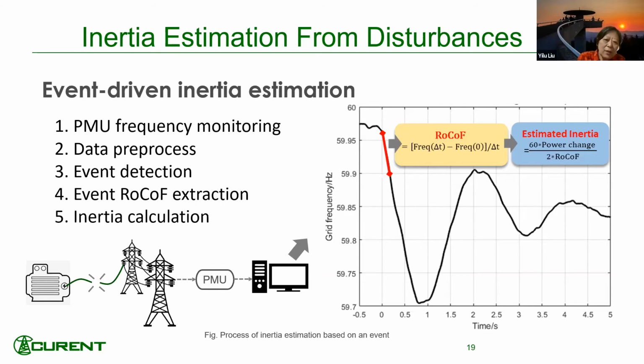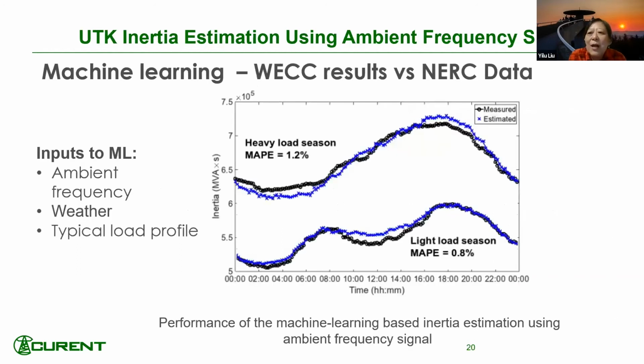I can actually monitor system inertia easily with collaboration with the utility company. If we're talking about real-time measurement, that's difficult because you don't have a trip every minute, and you don't want that to happen either. You have about one major generator trip maybe every day or every other day. That's typical, so you can't know your inertia every hour or every 15 minutes that way. But you can still monitor it based on ambient data.